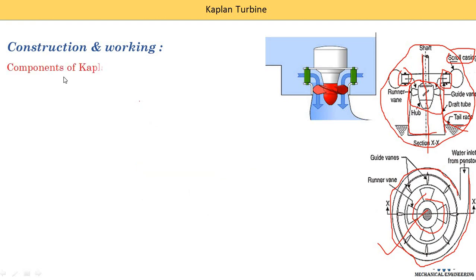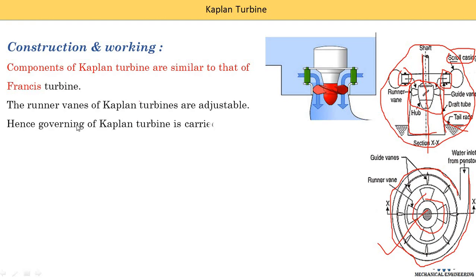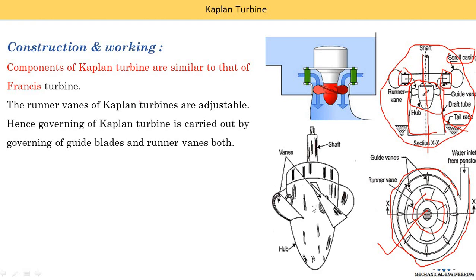The components of Kaplan turbines are similar to those of the Francis turbine. The runner vanes of the Kaplan turbine are adjustable. Hence, governing of the Kaplan turbine is carried out by governing the guide blade as well as the runner vane angle both. In the Kaplan turbine, the angle of these runner vanes is adjustable — the vanes are mounted on a hub that has a hollow component, and the vane angle is controlled by a servo motor mechanism. The guide vane angle is also changed, so governing uses these two methods: adjusting the guide vanes as well as adjusting the runner vane angle.